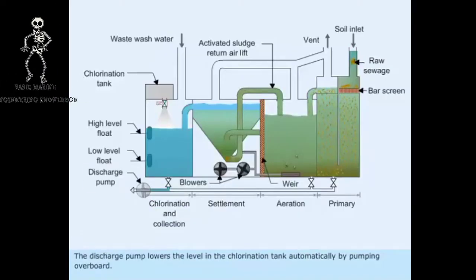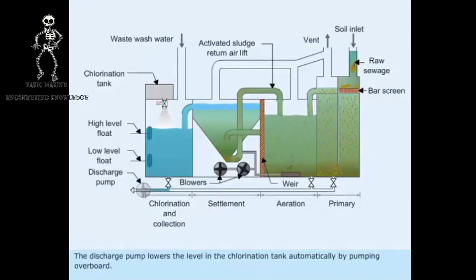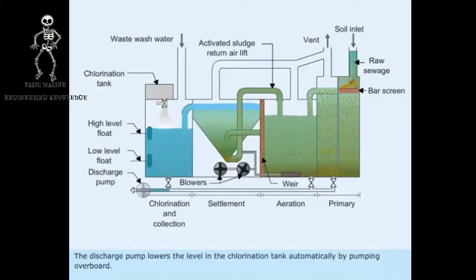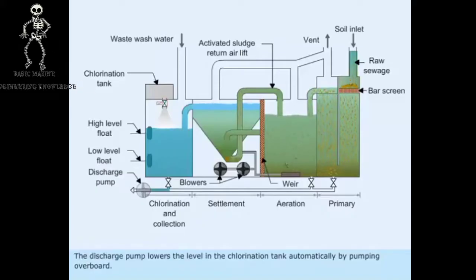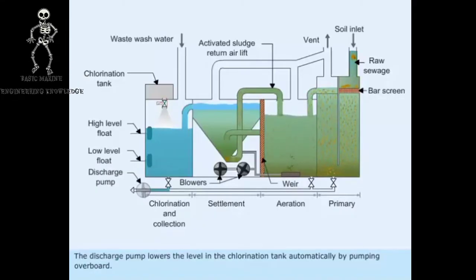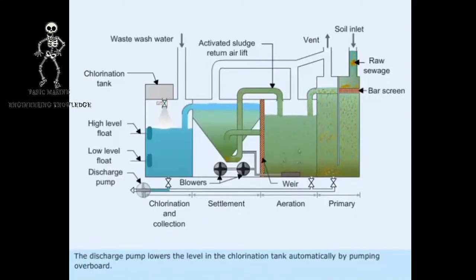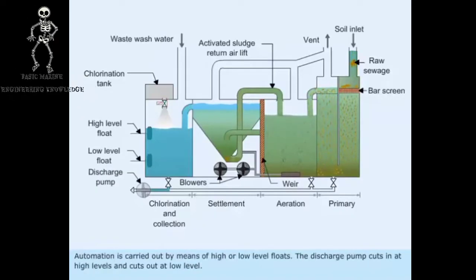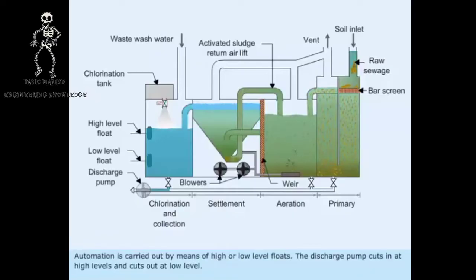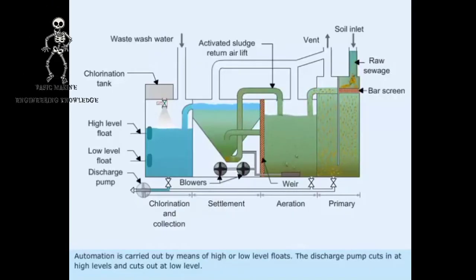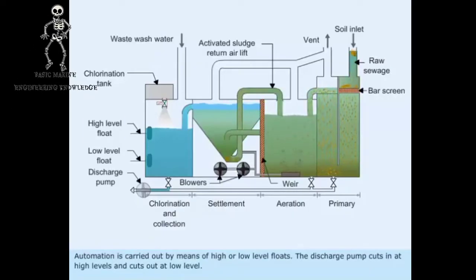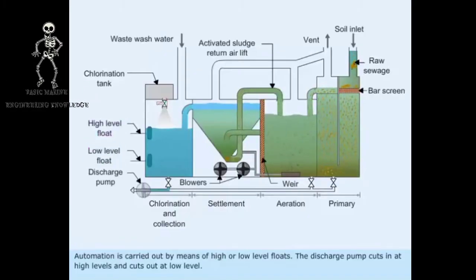The discharge pump lowers the level in the chlorination tank automatically by pumping overboard. Automation is carried out by means of high or low level floats. The discharge pump cuts in at high level and cuts out at low level.